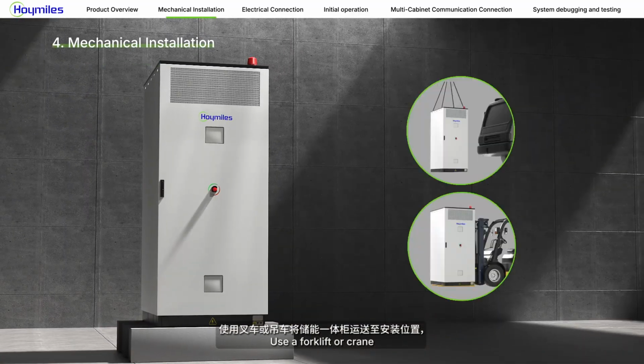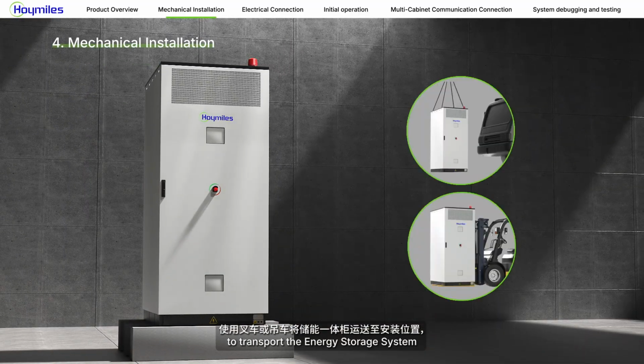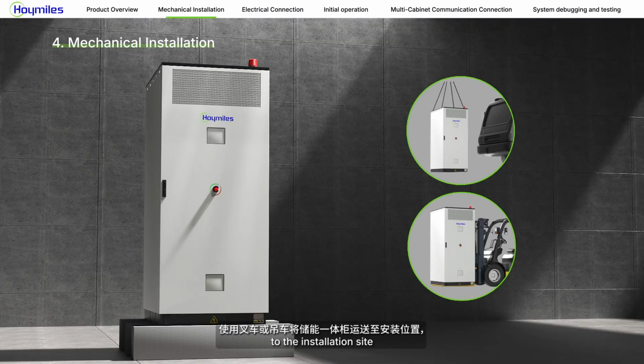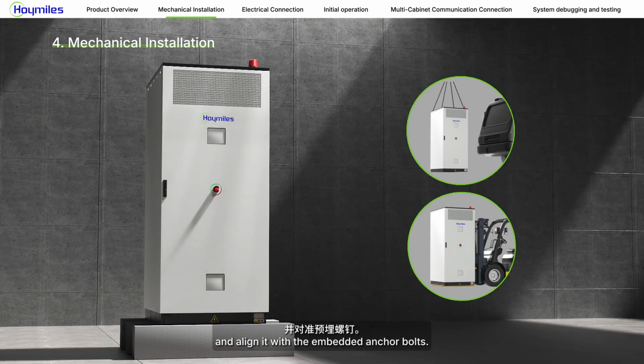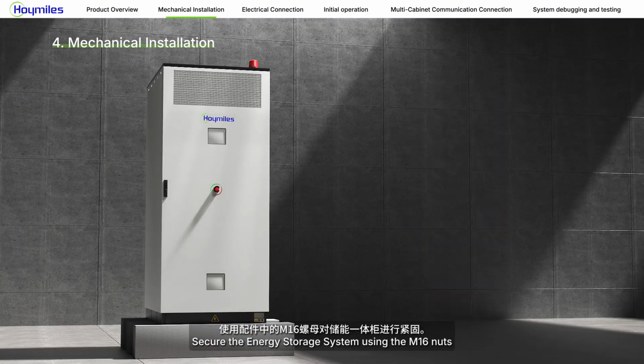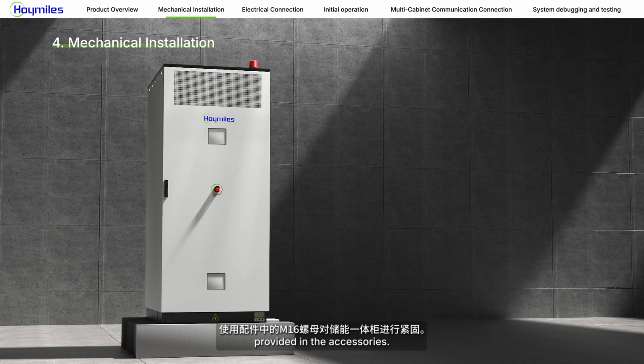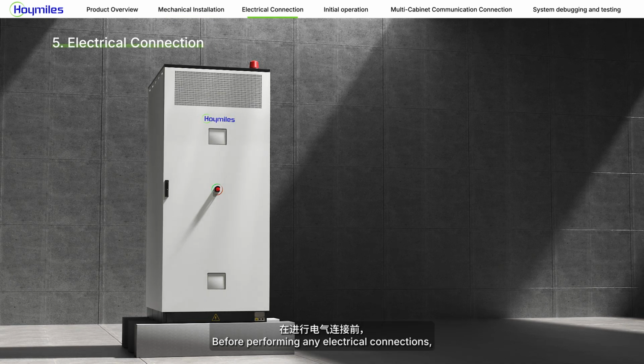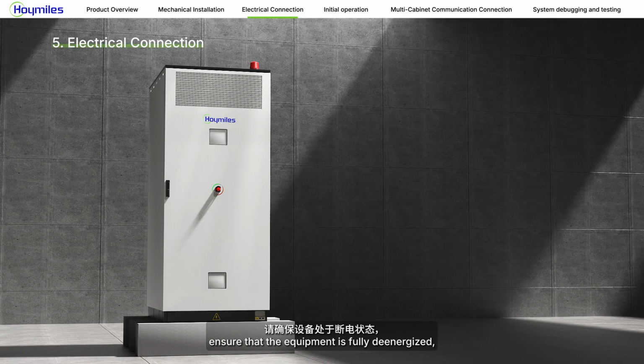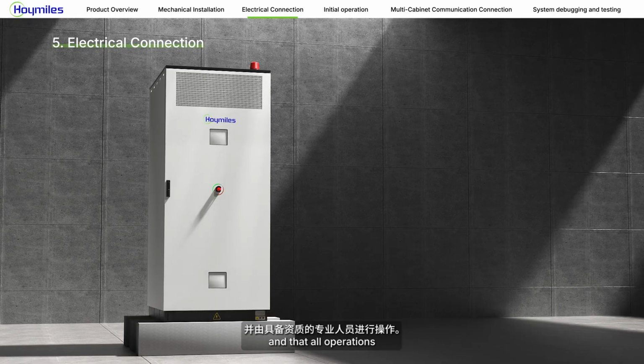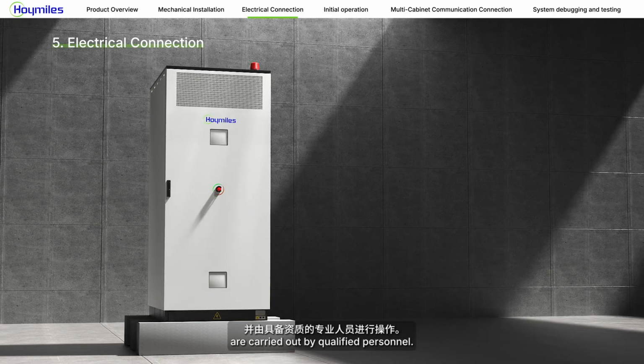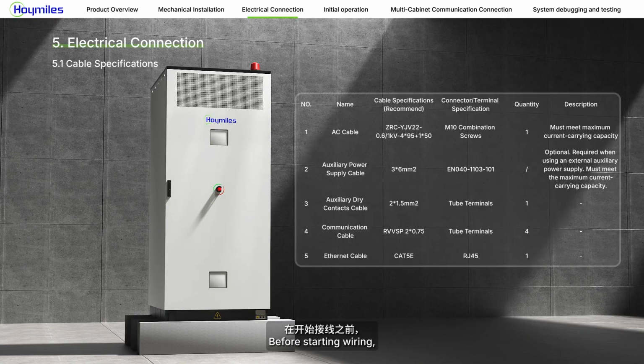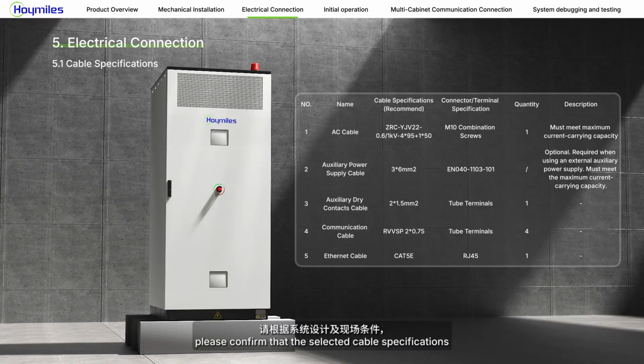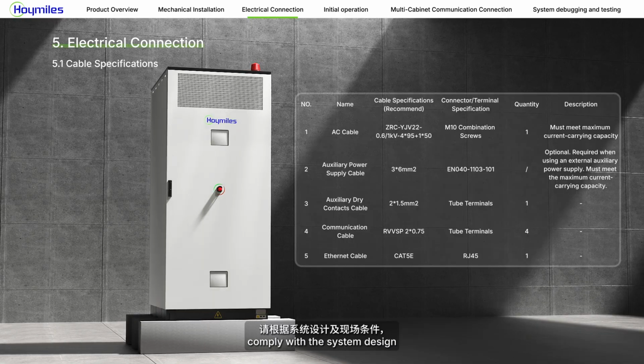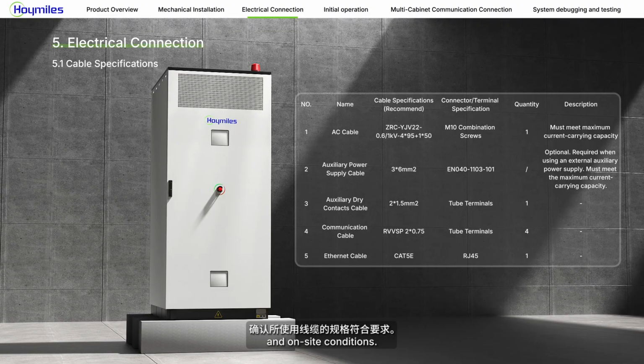Use a forklift or crane to transport the energy storage system to the installation site and align it with the embedded anchor bolts. Secure the energy storage system using the M16 nuts provided in the accessories. Before performing any electrical connections, ensure that the equipment is fully de-energized and that all operations are carried out by qualified personnel. Before starting wiring, please confirm that the selected cable specifications comply with the system design and on-site conditions.